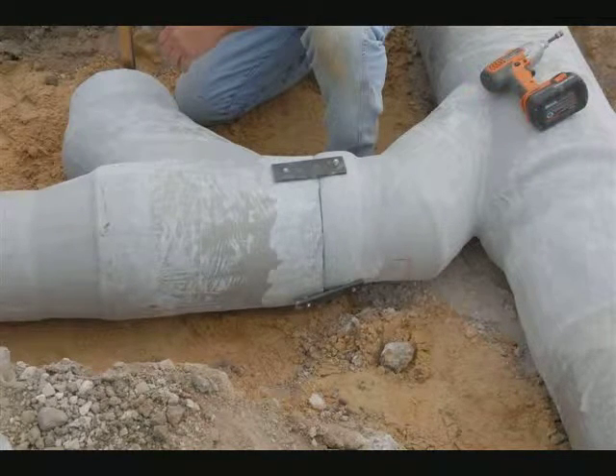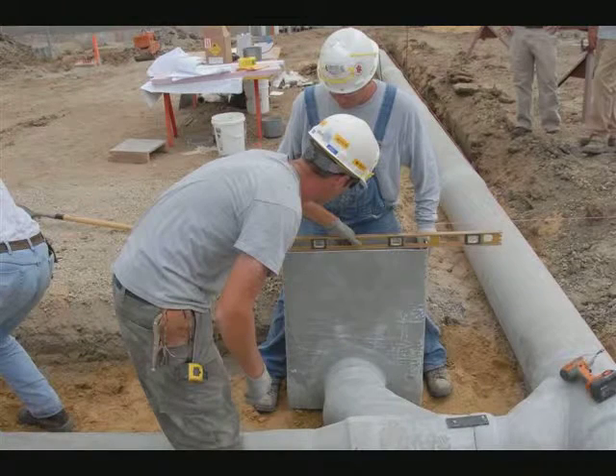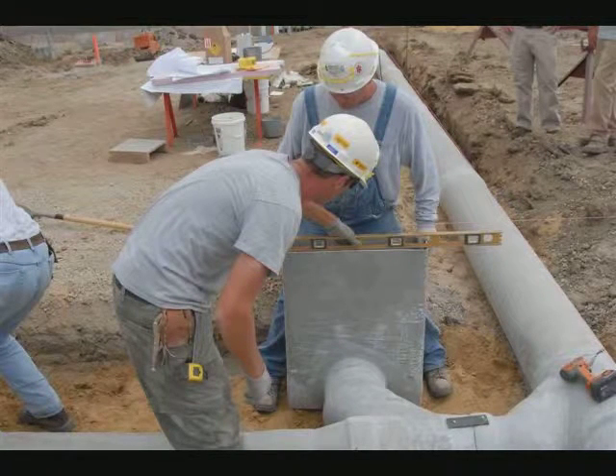You'd mentioned earlier that you pressure tested the duct before you backfilled it. Could you go into detail the pressure testing method that you chose to use and why that one? Here at Crawford we have a pressure testing fan. We just sealed up all the boots and the ends of the duct, and hooked the fan up to it to pressure test. There are formulas that you go by that let you know the amount of leakage. It was fairly simple, no different than a typical sheet metal duct system.